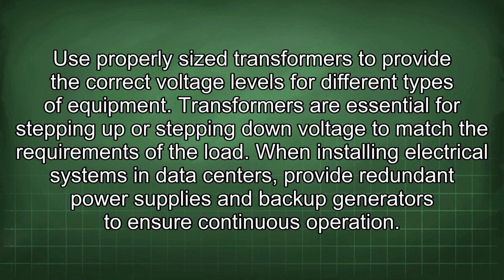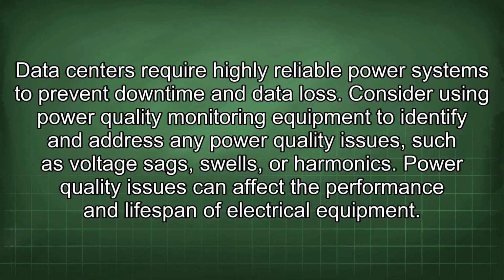When installing electrical systems in data centers, provide redundant power supplies and backup generators to ensure continuous operation. Data centers require highly reliable power systems to prevent downtime and data loss. Consider using power quality monitoring equipment to identify and address any power quality issues, such as voltage sags, swells, or harmonics. Power quality issues can affect the performance and lifespan of electrical equipment.